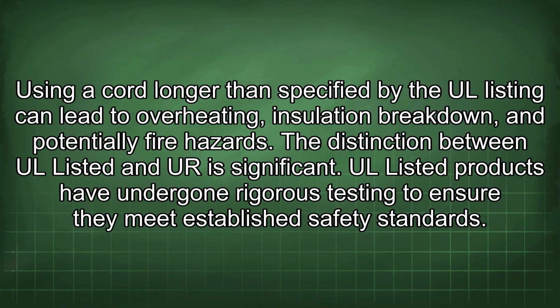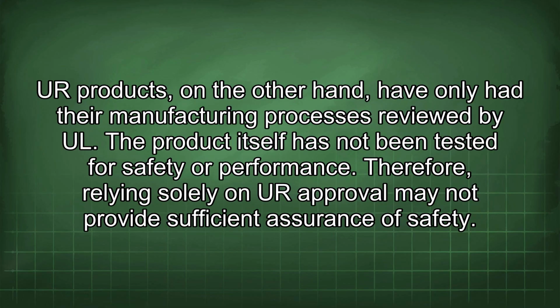The distinction between UL listed and UR is significant. UL listed products have undergone rigorous testing to ensure they meet established safety standards. UR products, on the other hand, have only had their manufacturing processes reviewed by UL. The product itself has not been tested for safety or performance. Therefore, relying solely on UR approval may not provide sufficient assurance of safety.